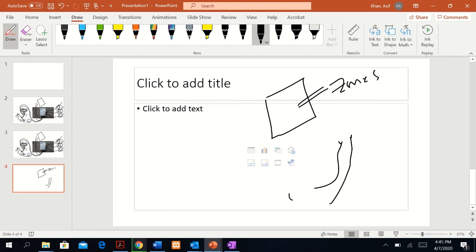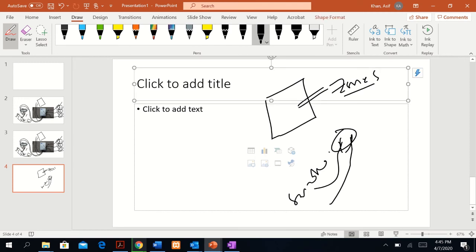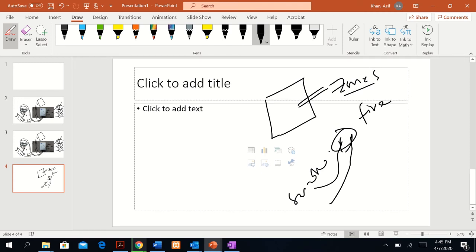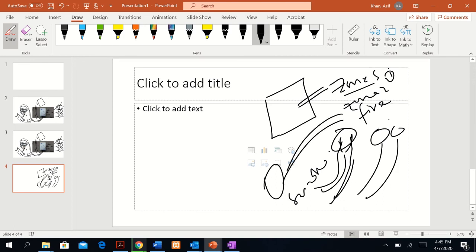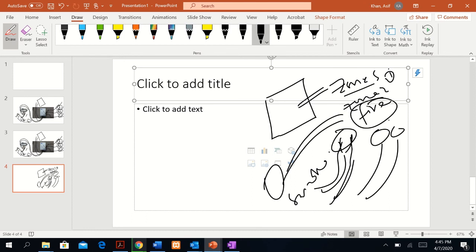And zones, let's say this is a smoke detector. You go to any of the first four zones and connect these wires, and then on the console screen it will say zone, the type of zone is fire, and you press enter. When you press enter, this zone is configured. Similarly, you can do the same thing for the other zone. You go to zones again, so this is zone 1, and there will be zone 2. If it is another smoke detector, you specify that it is a fire type sensor.